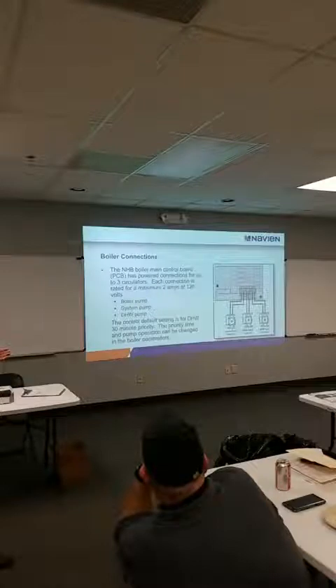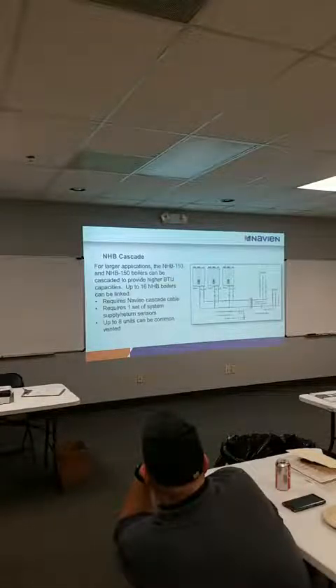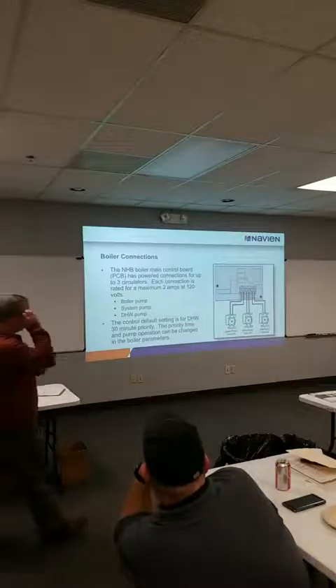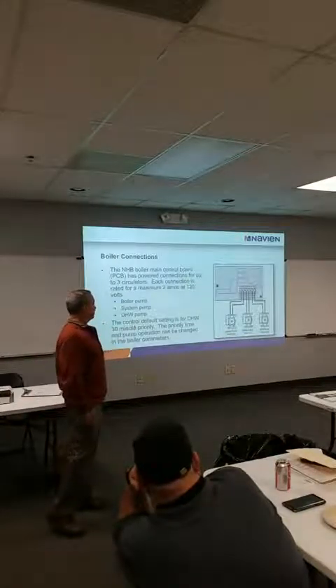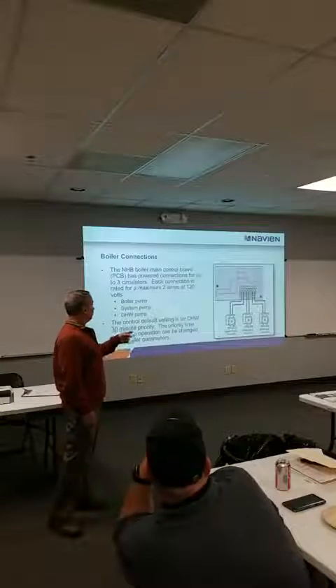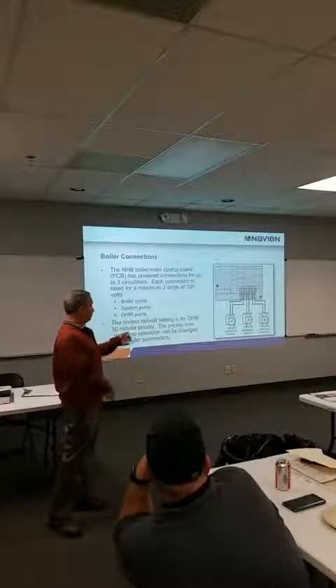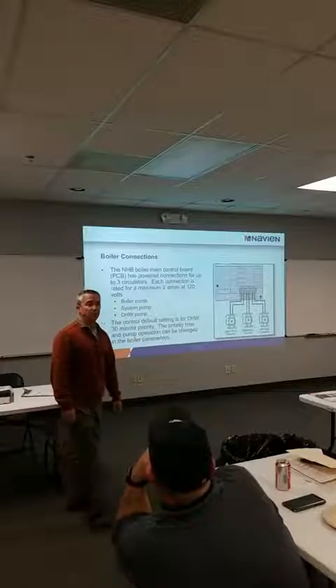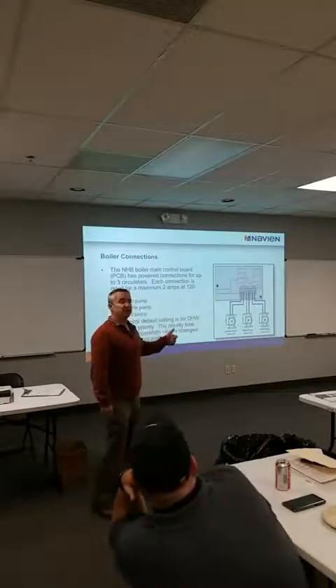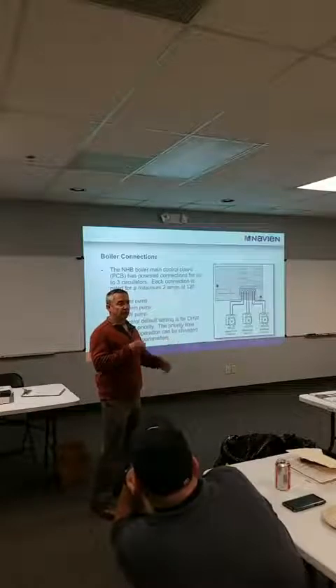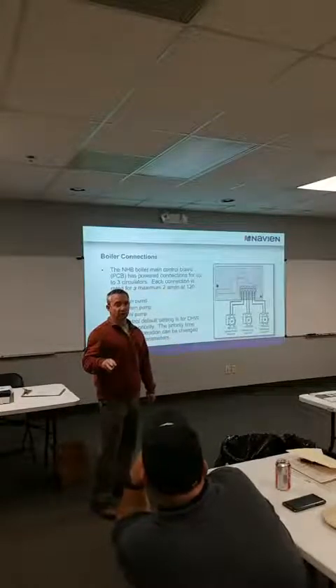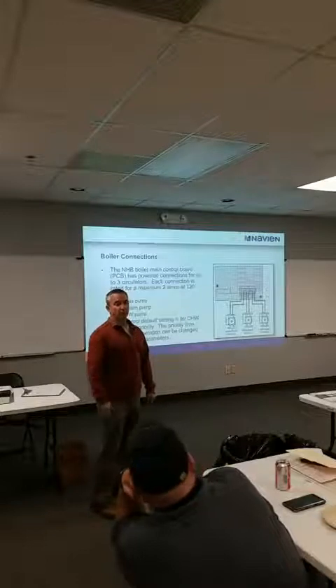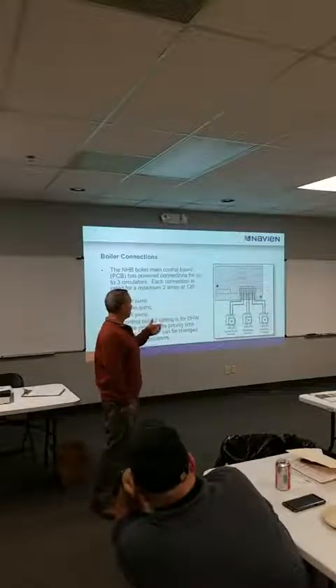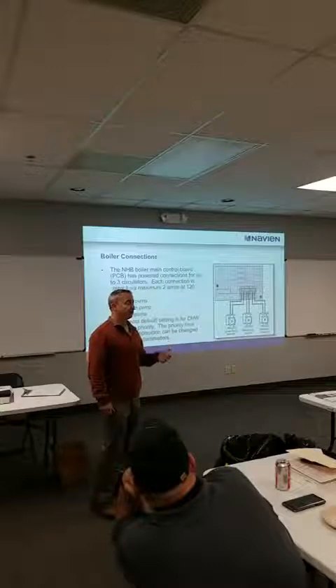So the NHB right now, we can only do zone pumps with, back to the board, and we're limited to those 3 pumps. Basically, a system pump, boiler pump, and a domestic hot water pump, you know, one of the 3, but that's what we're maxed out on this board right now. When we do our board upgrade to this unit, the new electronics board will give you 3 system pumps, 3 system zone valves, plus a boiler pump. And all our domestic hot water pumps, you can program in priority too with a separate temperature.